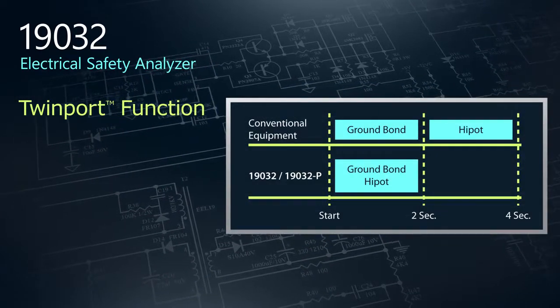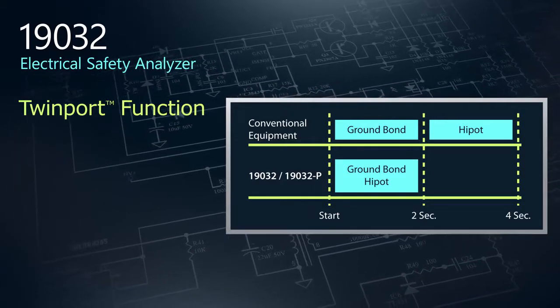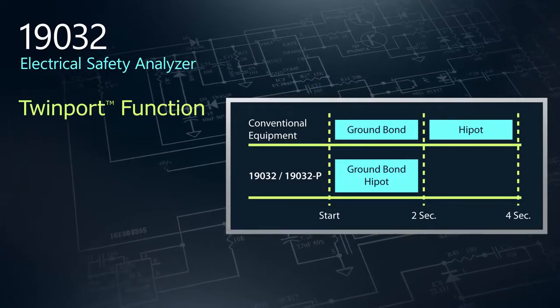To increase efficiency, we introduce TwinPort, a patented function that performs simultaneous hipot and ground bond tests, eliminating potential bottlenecks in the production line.